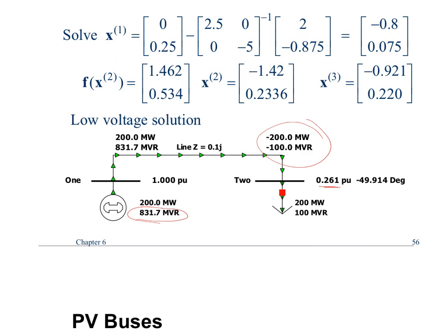So the way that you do that is you have massive amounts of current flowing through this system, and you get a huge I squared X to give you the voltage drop you want. It does meet the criteria, but in the real world it wouldn't happen because if you ran the line with that much power loss, you'd say bye-bye to the line, right? It wouldn't exist very long. Yeah, because it's all I squared, so it's the magnitude of I. So your P and your Q determine the magnitude of the current.